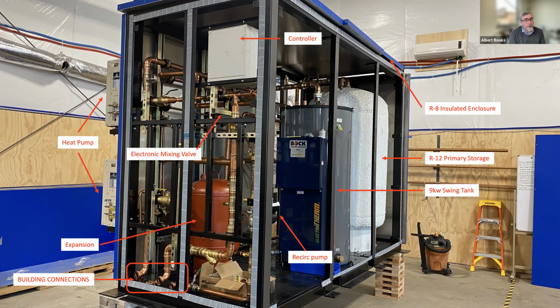heat pump. Aaron's asking what sort of factory testing occurs to ensure system functionality to specs to reduce risk. Well, pressure check. As far as functionality to specs, for us, the packages that we're creating are the same packages that we've done in site-built systems for years. So there's not really a lot that we have to do because we already know, and the utility knows how these systems work. It's just, can you get it to site without a leak? And can your installing contractor get it set up? And at startup, we'll actually see the functionality.